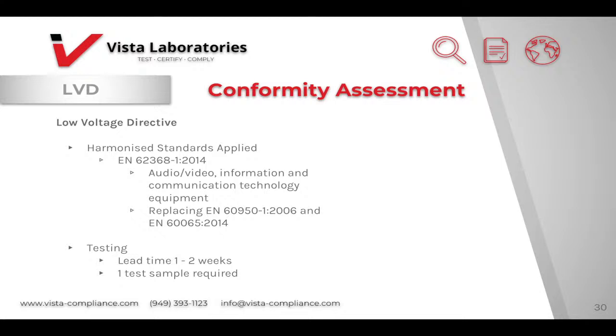The new approach in IEC 62368 focuses on demonstrating consideration of known hazards and that the product is designed to be safely operated in that context, as opposed to IEC 60950 and IEC 60065, where the emphasis is on whether the prescribed specifications have been met. Though hazard-based, 62368-1 does not require risk analysis like IEC 60601-1. For testing, the lead time is 1 to 2 weeks and 1 sample is required.